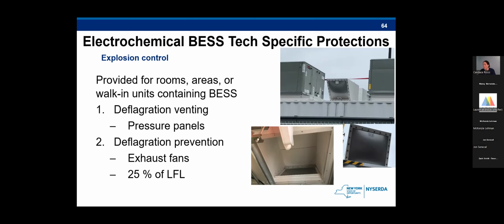That blast wave will be sent through the venting panels and should maintain the integrity of the container. And these panels' venting direction should be directed to an area that will not interfere with the fire department's operation. And then you have the deflagration prevention, which can be done using exhaust fans and limiting the lower flammability limit to 25%. And once again, this is the requirement that you will see having applicants putting exhaust fans and ventilation in their lithium ion systems.